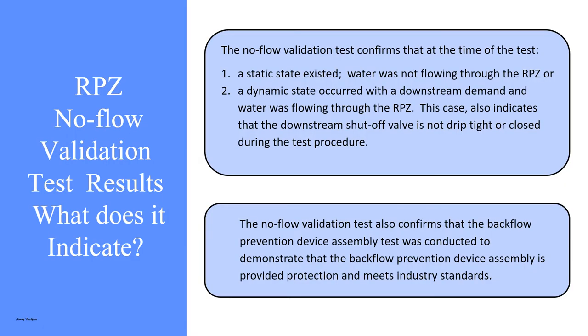RPZ no-flow validation test results. The no-flow validation test confirms that at the time of the test: one, a static state existed and water was not flowing through the RPZ; or two, a dynamic state occurred with a downstream demand and water was flowing through the RPZ. This also indicates that the downstream shutoff valve is not drip tight or was not closed during the test procedure. The no-flow validation test also confirms that the backflow prevention device assembly test was conducted to demonstrate that the assembly is providing protection and meets industry standards.